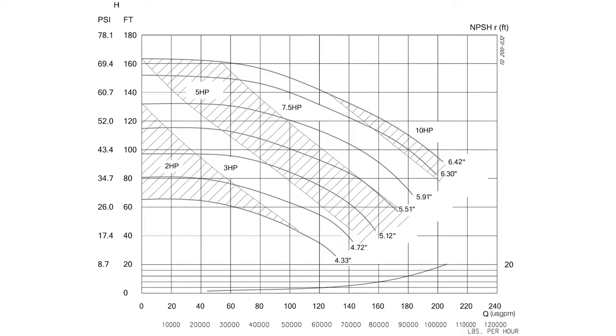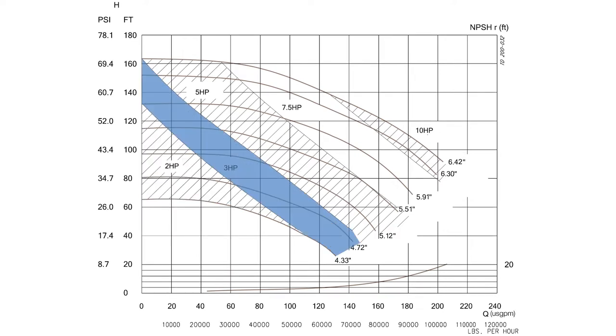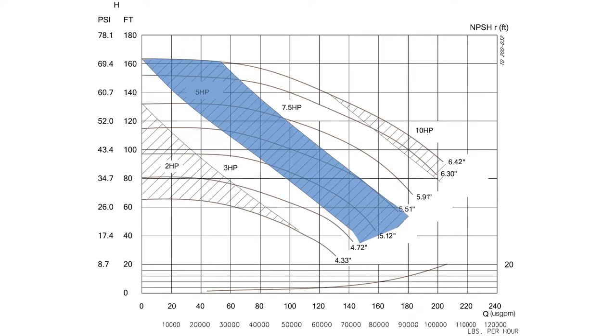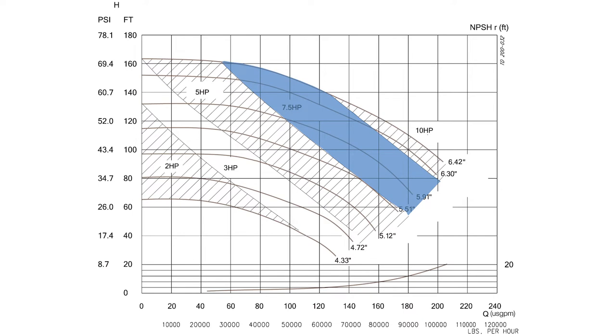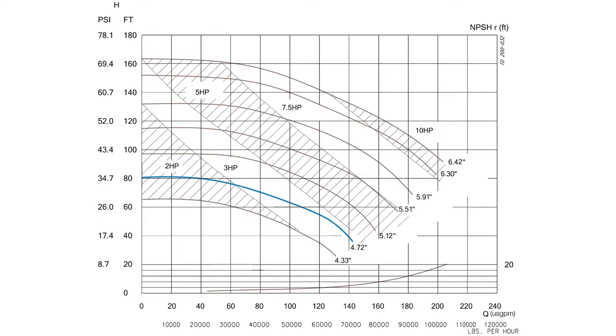Because some pumps can operate at a range of horsepower, curves may include additional information to account for the range of a pump's performance. This curve features a pump that can operate from 2 to 10 horsepower depending on the desired performance. On this graph, each curve represents a typical impeller size for this pump, ranging from 4.33 inches to a full size 6.42 inch impeller.